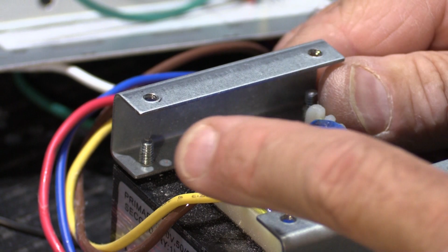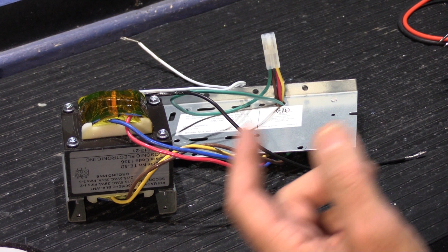Now the question is, is there a fuse on this side, and is that side blown or not? I think the way we can check that is by doing a continuity check on the low voltage output when it's powered off, so let me set that up. I don't know if there are any fuses on the output, but I have a feeling there's not, because if there was, there would have been a second fuse fusing the output of one leg of the secondary side into either the red or blue wire. So I have a feeling the only fuse is on the input here.